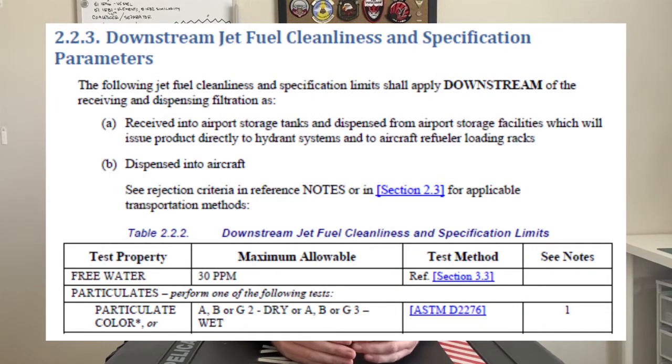Now for parameters. According to the latest revision of ATA 103, the acceptable limit of free water in jet fuel downstream of filtration is 30 parts per million. Here's where it gets interesting: our primary detection method for free water is visual, and the acceptable limit is 30 ppm, but at certain temperatures water may not be visually detectable until it reaches 40 parts per million. So you might be looking at a sample that is completely clear and bright, but it still may have a free water content higher than the acceptable limit. If you see water in a fuel sample, it is already far beyond the acceptable limit.